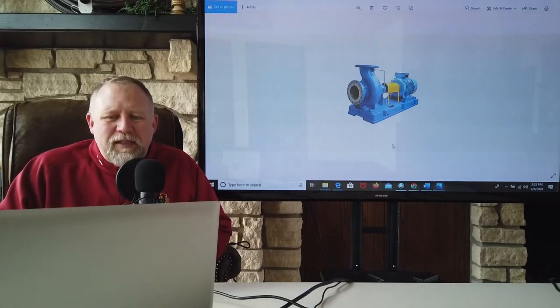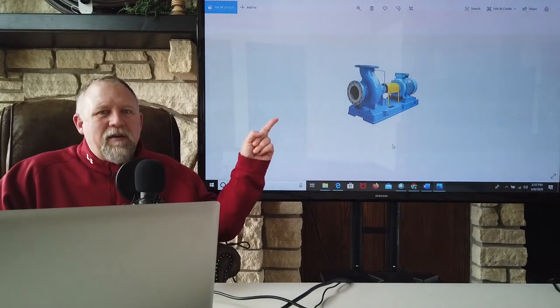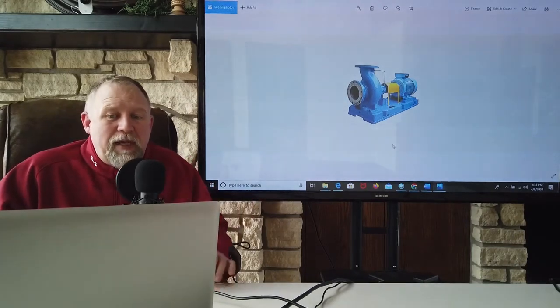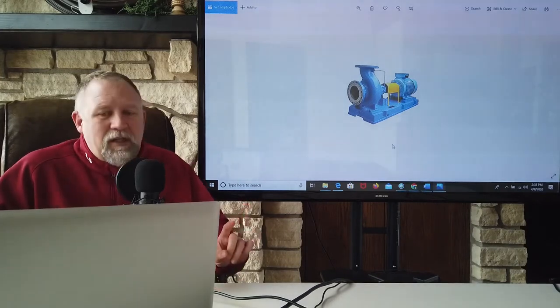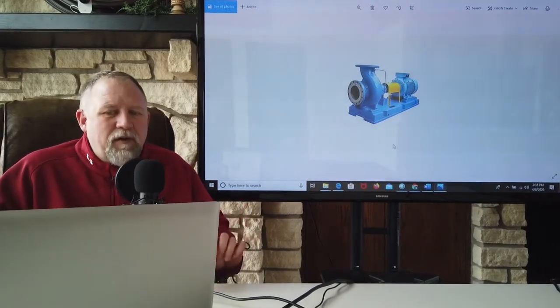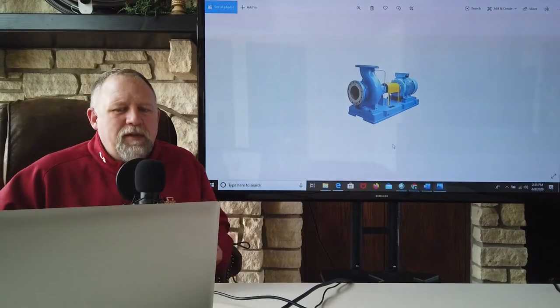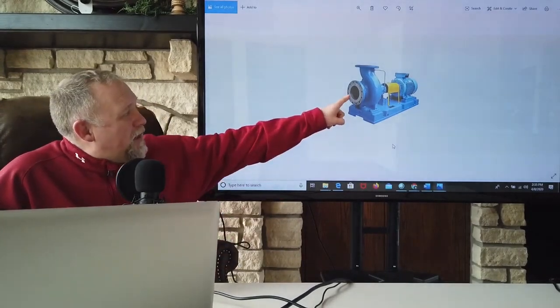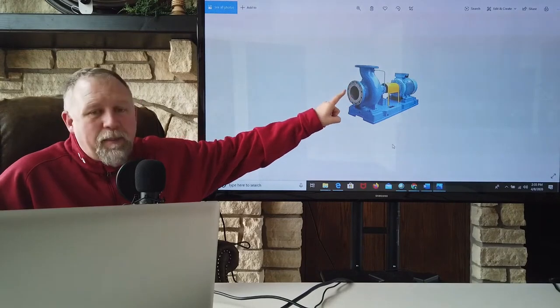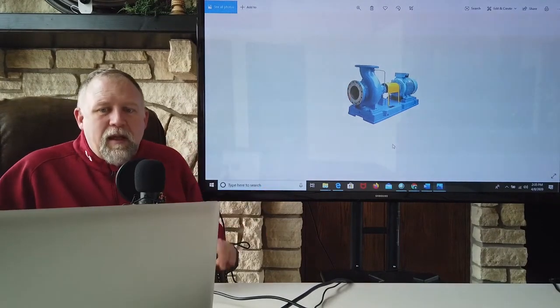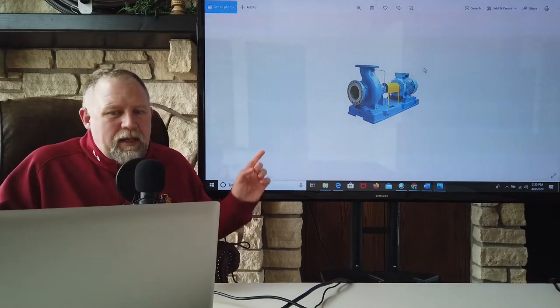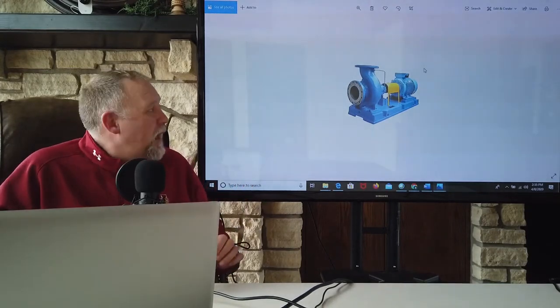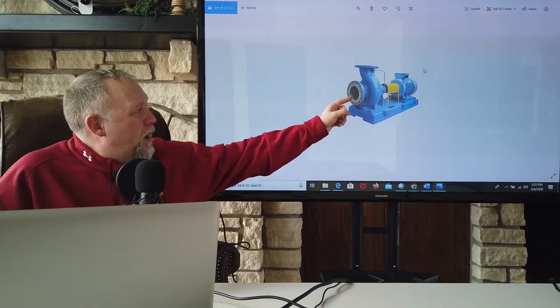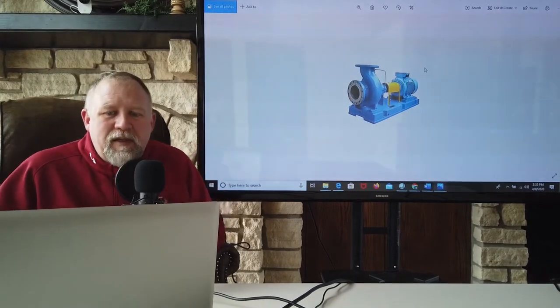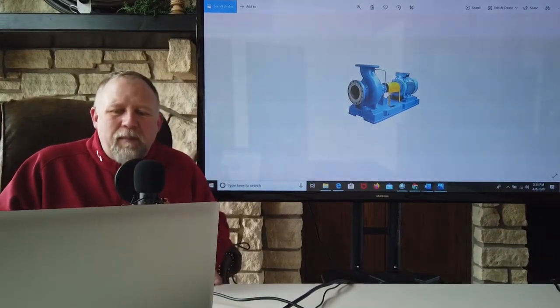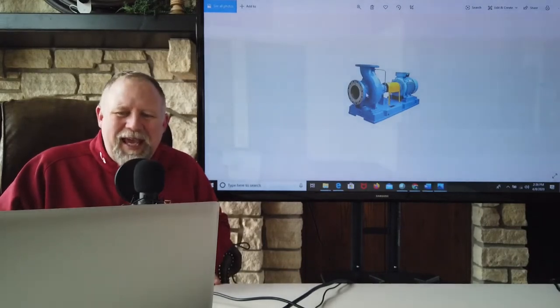So first, this is the picture that I have here and that I have loaded onto the Canvas page. This is an end-suction top discharge centrifugal pump. Some important parts about this. Right here, the end-suction. There would be a pipe here, right? We connect that to a pipe and it would actually suck water in here into the center of this pump. Then it would go into the impeller. The impeller is the part that you can't see.